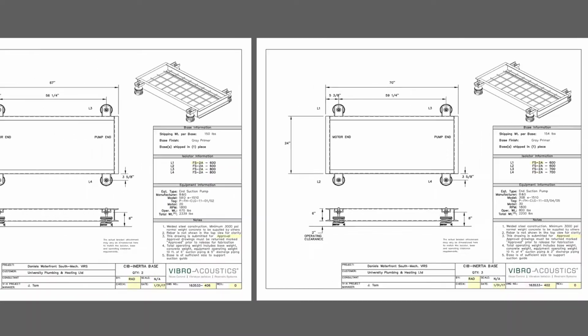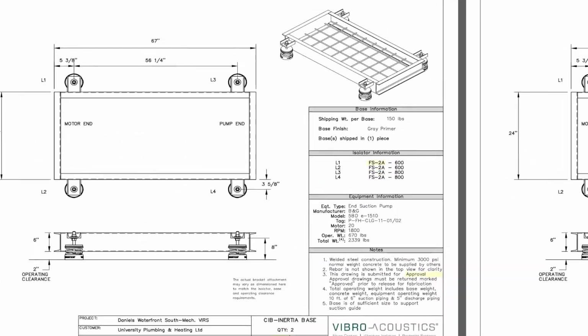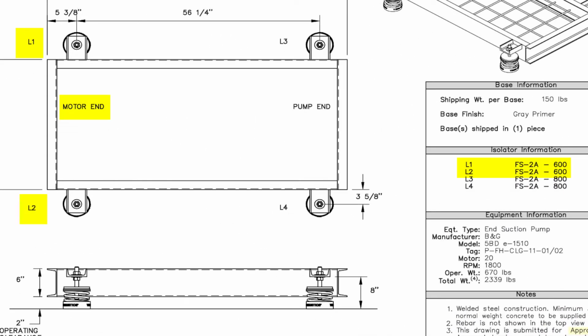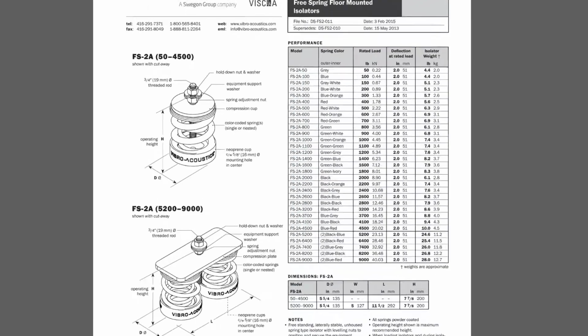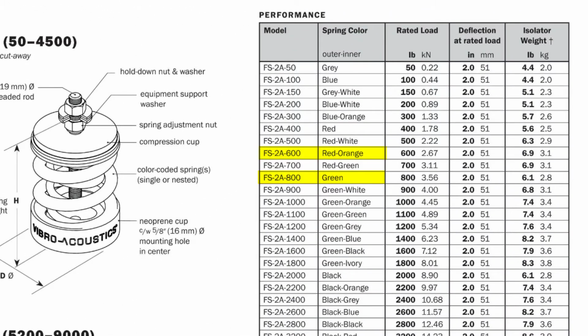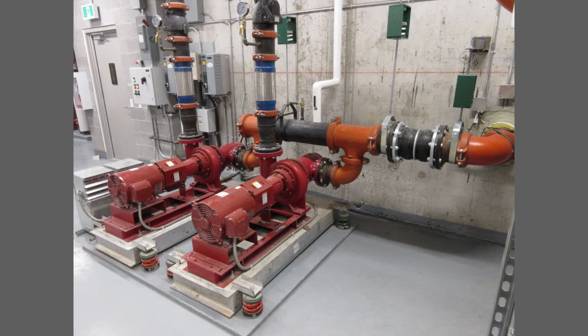We're going to look at the condenser water pumps first. Per the submittal, there should be FS2A 600s on the motor end and FS2A 800s on the pump end. Referring to the FS2A datasheet, we see that the 600s will have red outer and orange inner springs, and the 800s will have just a single green spring. Here are the condenser water pumps on their inertia bases. I'll go ahead and note that the green springs are on the pump end and the red and orange springs are on the motor end, as shown in the submittal.